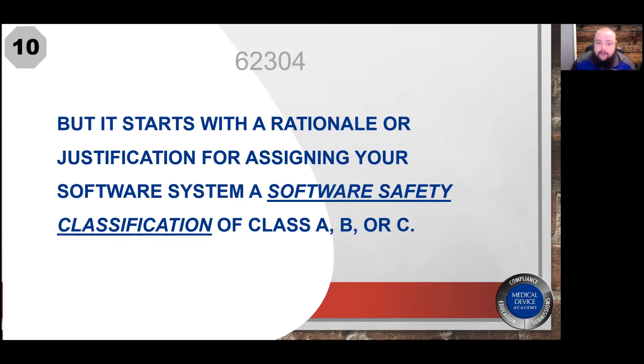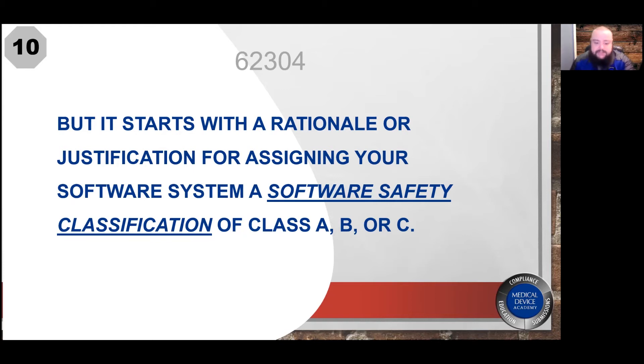But before all of that, it begins with a rationale or justification for assigning your software system a software safety classification. That classification will result in a class assignment of A, B, or C, and this is done according to the risk of harm from a hazardous situation that your software system could contribute to in a worst-case scenario — excluding special rules for decomposed software items that have been specially segregated and rationalized for independent classification from the software system.